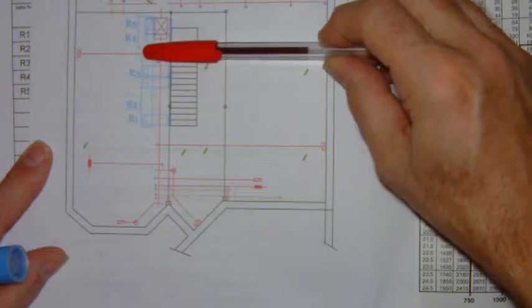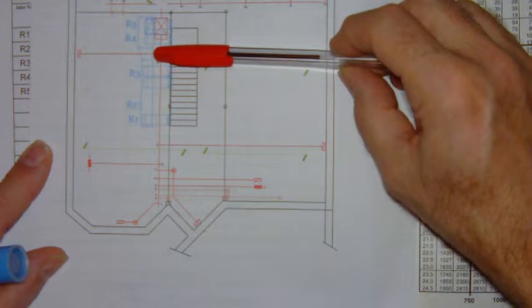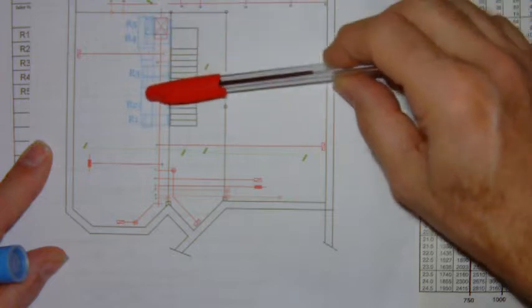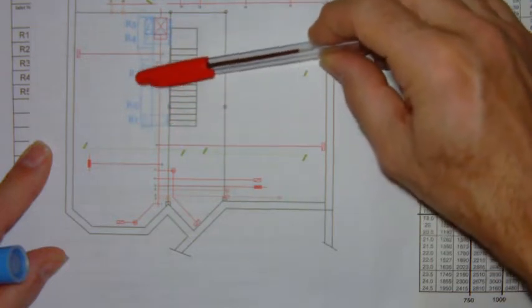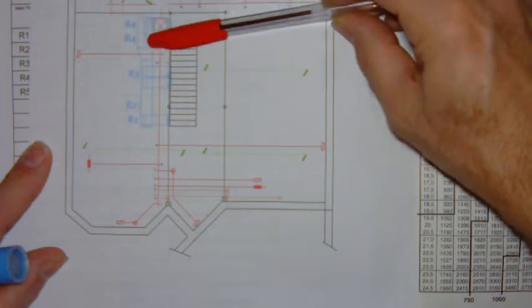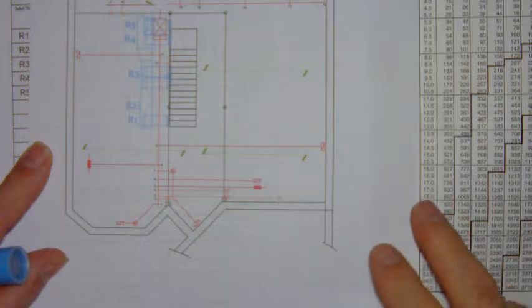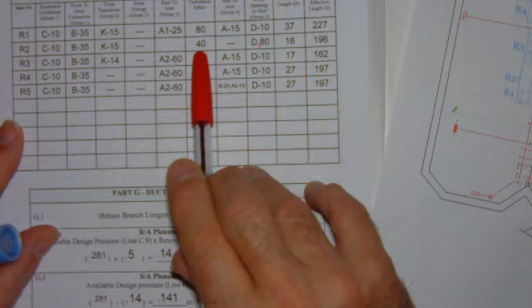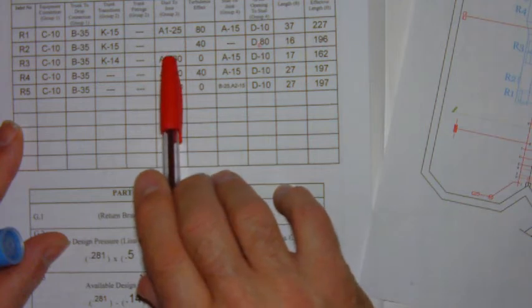The next point of interest in this duct is this transition. Now the transition has the effect of eliminating the turbulence beyond it. So any turbulence or the air from R1, 2, or 3 no longer experiences turbulence in the larger duct. So because R2 only intersects with R3, we would add a 40 for the turbulence. Now, as I mentioned, there is no duct to joist or joist to duct, and so that particular box remains blank.